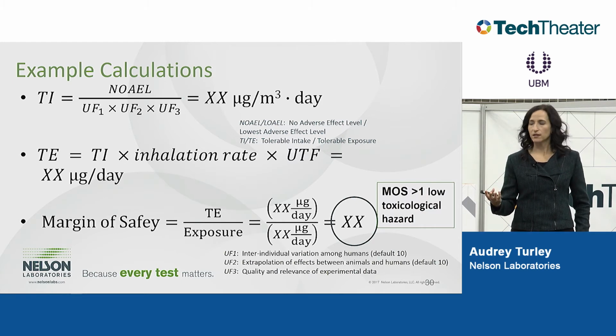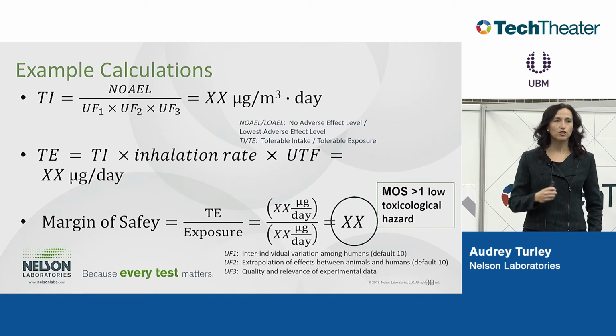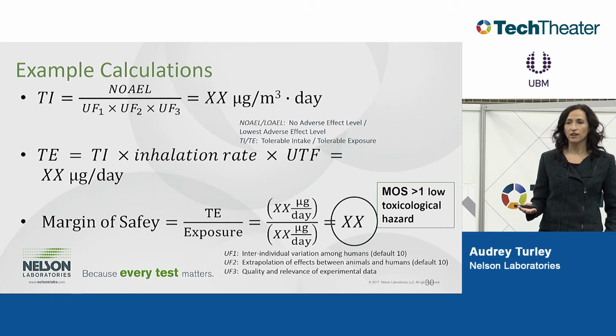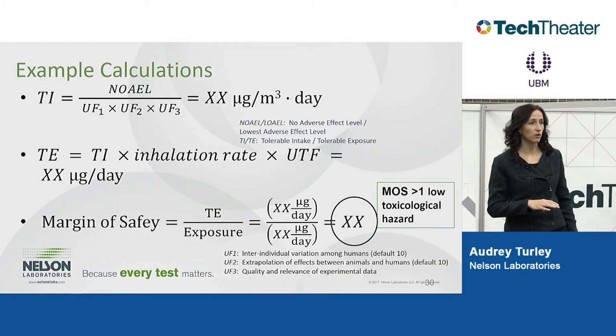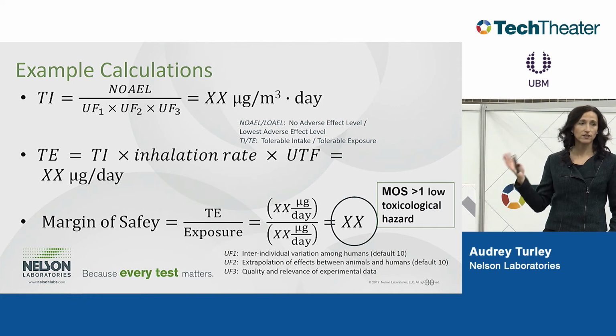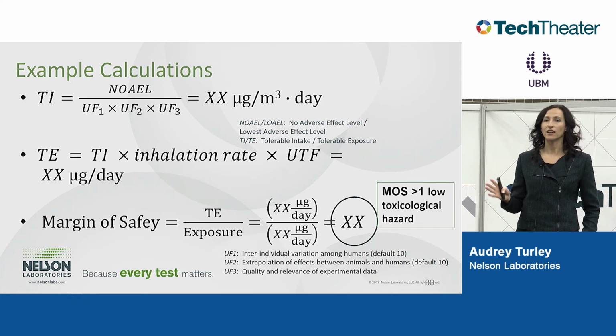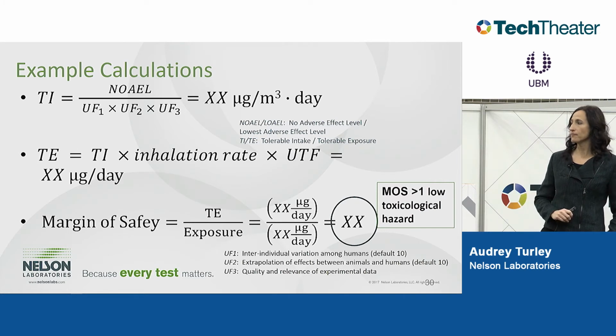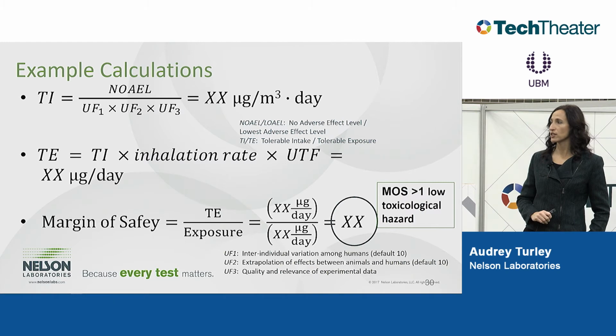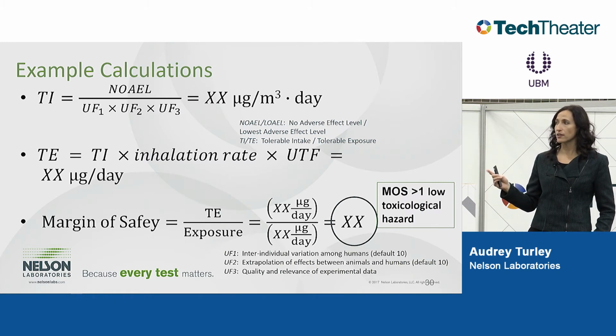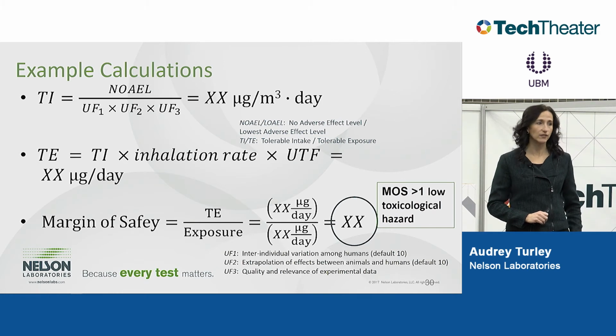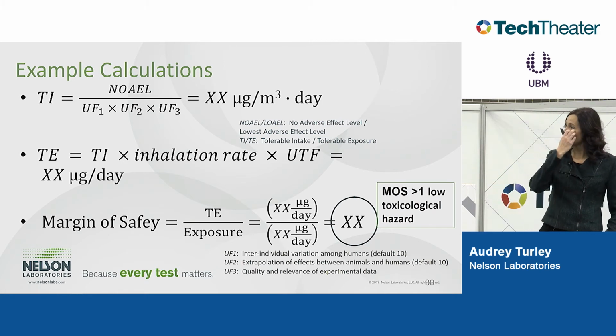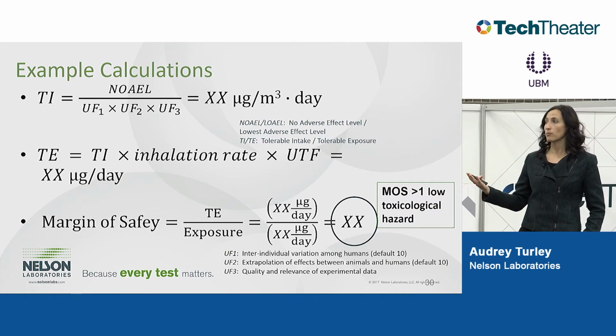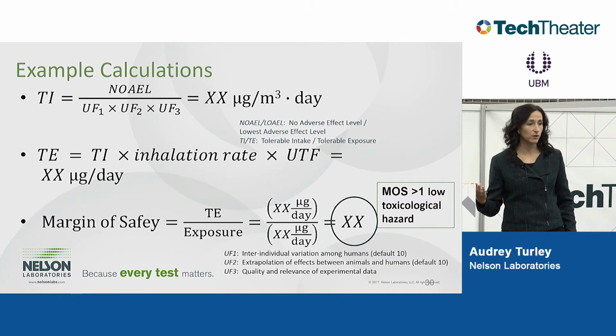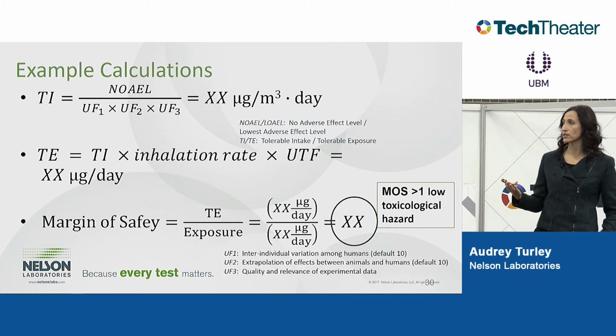So most of the published literature is not going to have a lot of inhalation data for some of these compounds. So we might find something that had an oral exposure. Well, that doesn't translate very well to an inhalation exposure. So we adjust our uncertainty factors. The toxicologists adjust them appropriately, understanding the appropriate risks. And then, of course, there's inter-individual variation that we will see. And there are default values that are set for a couple of these that are published in 10993-17. And then we get a value that equates to so much of this compound per day that a patient or a person could be exposed to, where we wouldn't expect to see anything adverse.